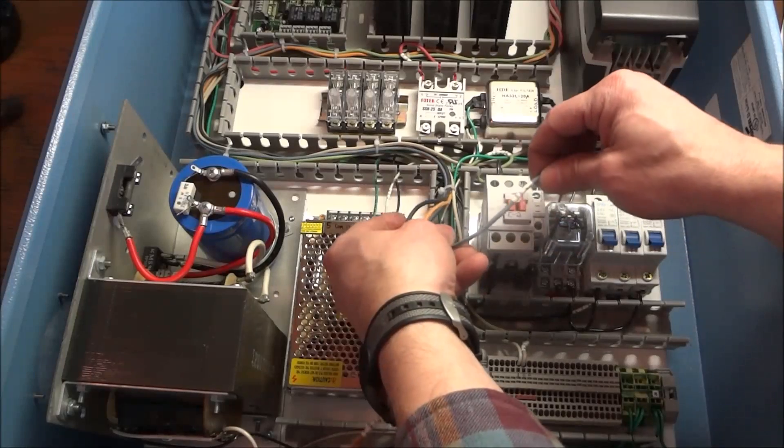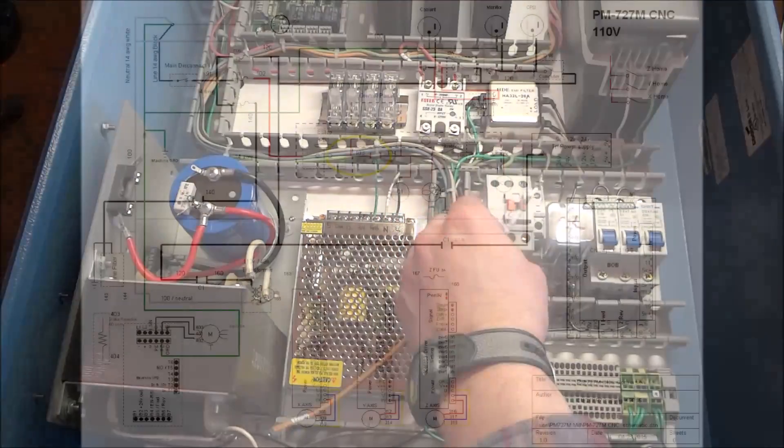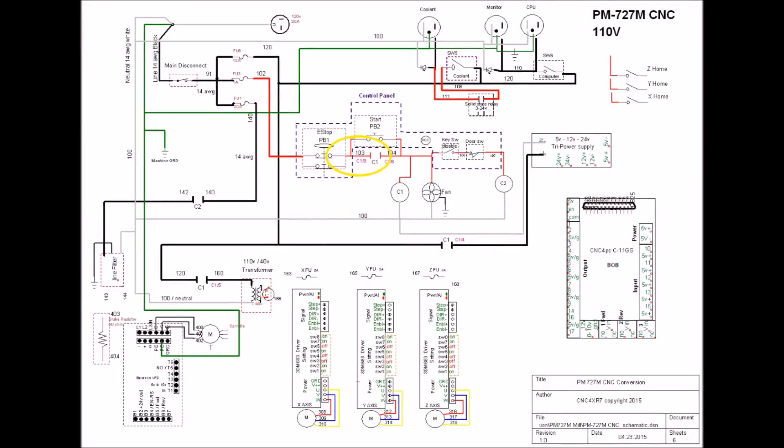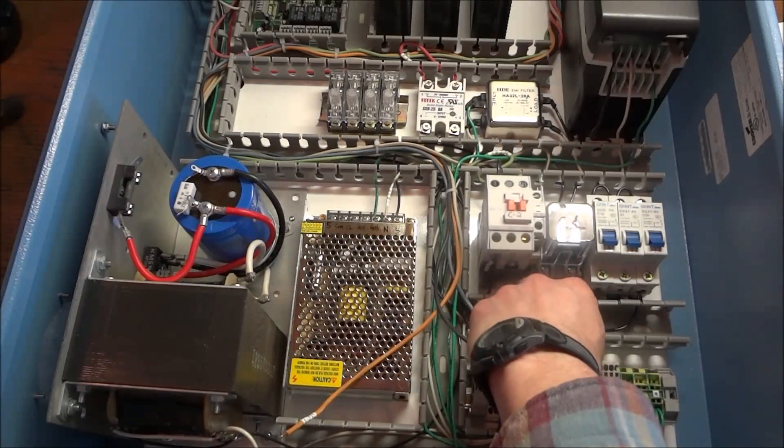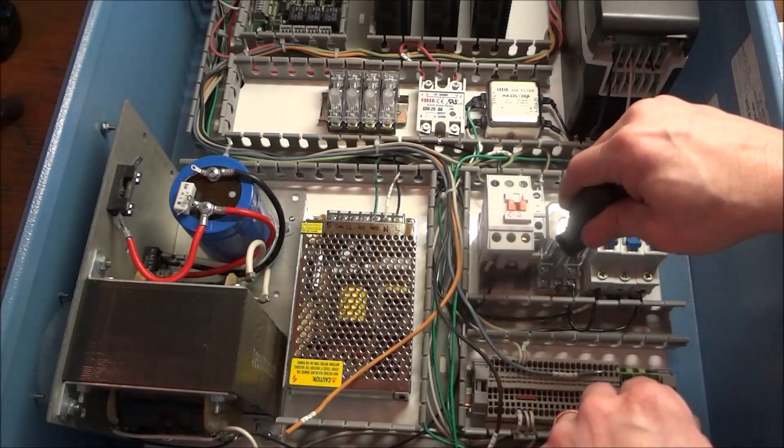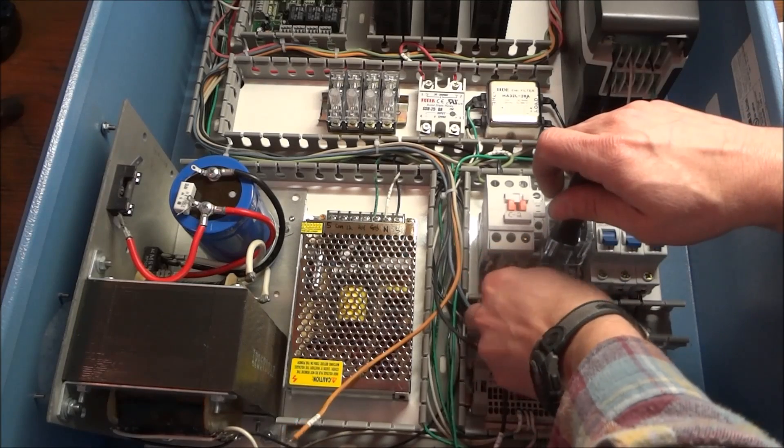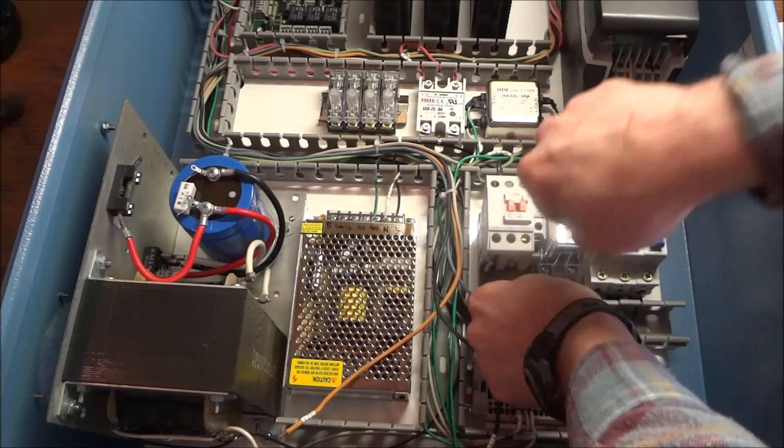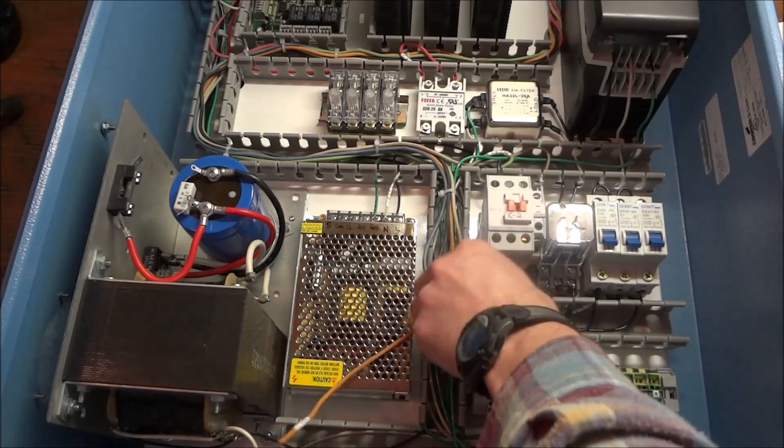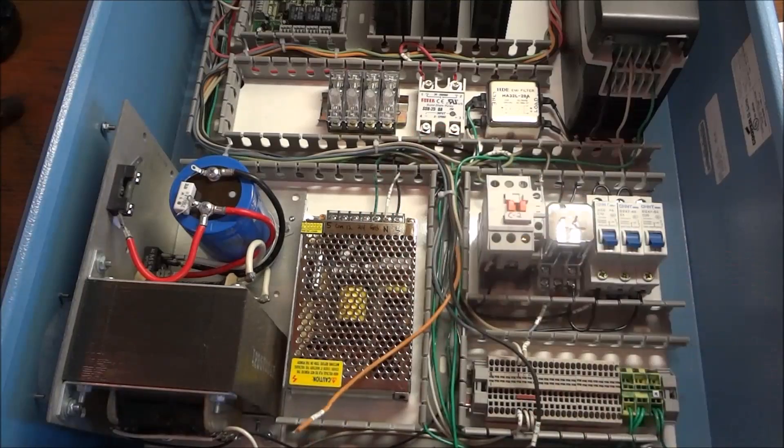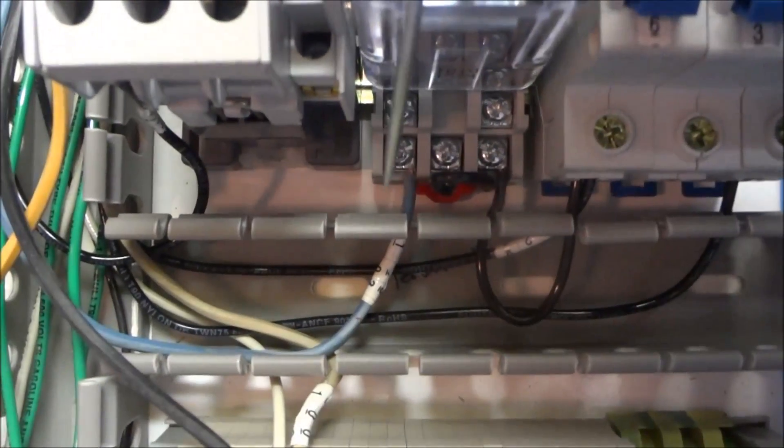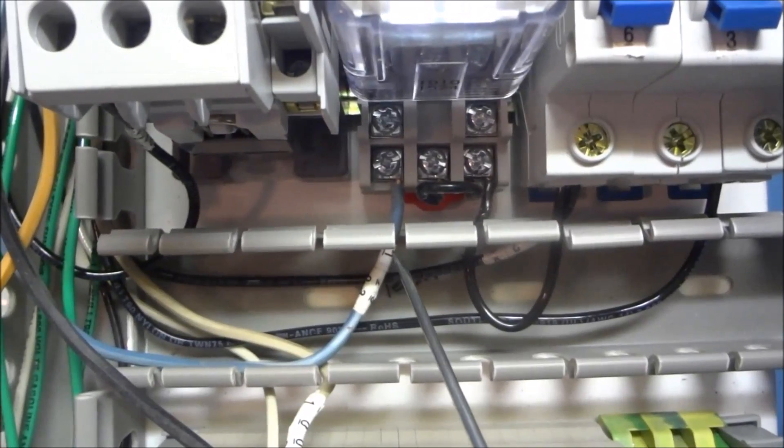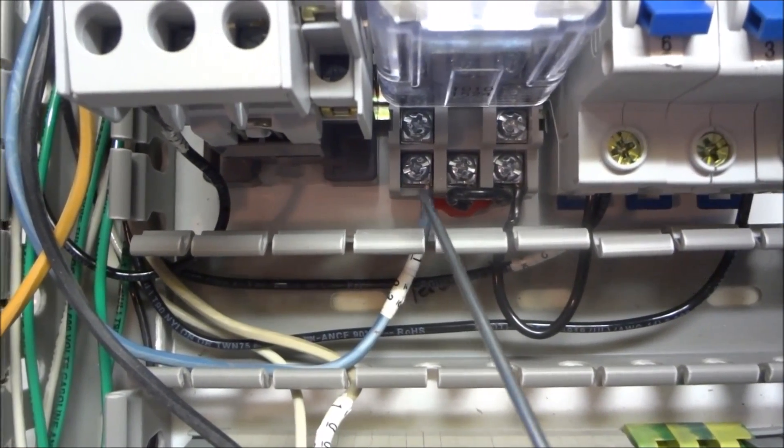Next we have our blue wire which is 103. Goes to the other side of our C1 contactor for our holding circuit. It's C1 terminal 9. And that's down here on the bottom. C1 terminal 9.